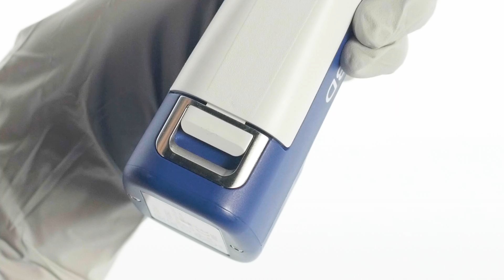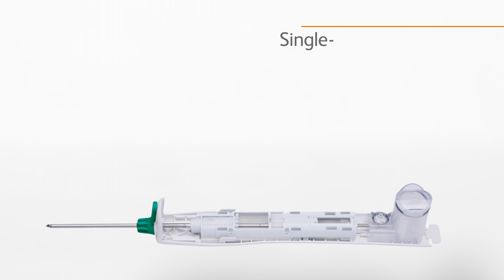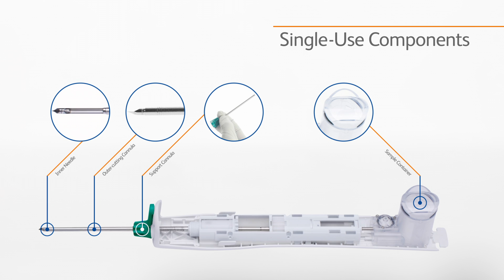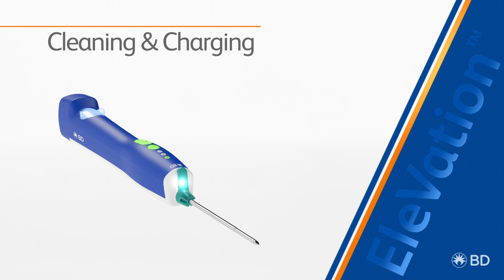After the procedure is completed, remove the probe from the driver. Press down on the locking tab, then slide the probe cover forward, pulling the probe straight up from the driver. Remember, the probe, cannula, sample container, and any needed accessories are intended for single use only. Handle and dispose of these items as a potential biohazard. After each procedure, clean the driver thoroughly with a germicidal disposable wipe. After each use, make sure to place the driver on the charging stand.